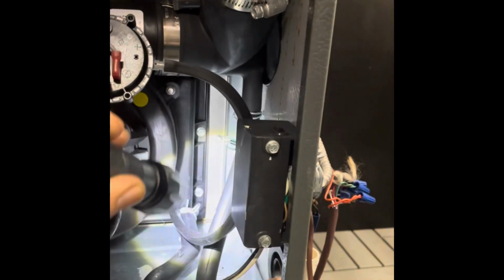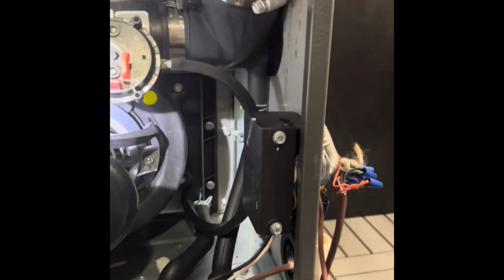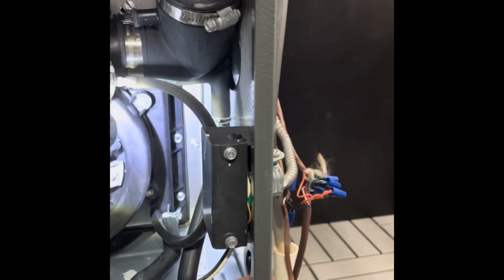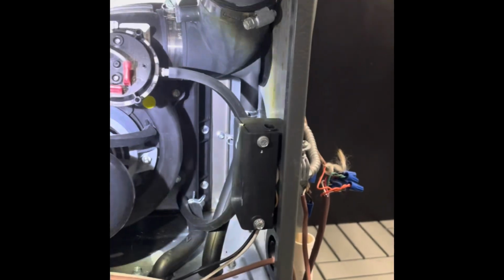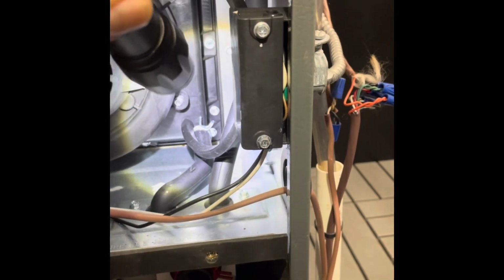There's one coming here. I'm gonna undo it at the fitting. I'm gonna blow air in that side and make sure that's not plugged up. I'm also gonna blow air in this hose into this fitting, making sure again that's not plugged up. Now with this particular unit, we do have a drain hose on the right side here. That's for our venting system. I want to remove that clamp, clear the hose, clear the fitting. I'm also gonna do the same with this hose coming off our collector box.